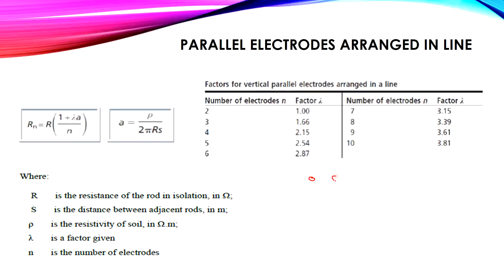If the electrodes are arranged in a line — electrode, electrode, electrode, connected by conductors — the same formula applies: R = R₁ × (1 + λA/n), where n is the number of electrodes and λ is obtained from the table. For three electrodes in a line, λ = 1.66.